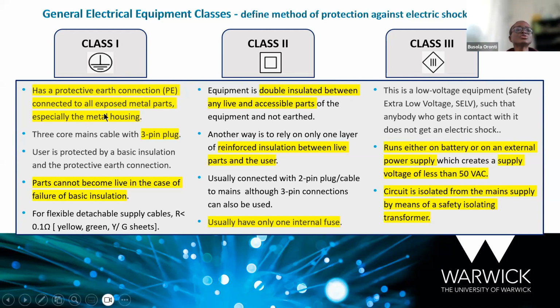So the basic thing to know about a class 1 equipment is that apart from the insulation, we also have what we call the protective earth connection, the PE. That's when you have a 3-pin plug. If you have a 3-pin plug, then you will have an earth connection. So if the insulation breaks down for any reason, the parts of the equipment cannot become live, because whatever extra current you have will go through the earth.